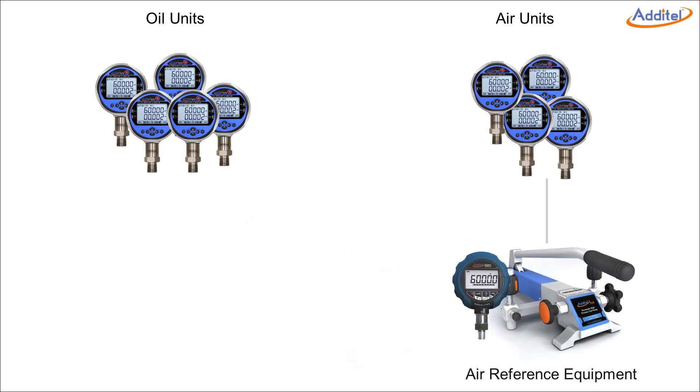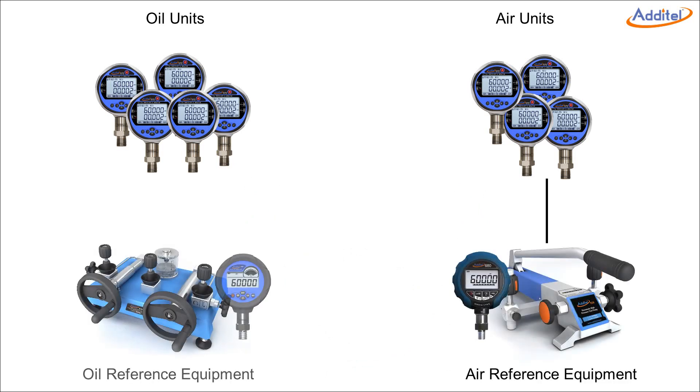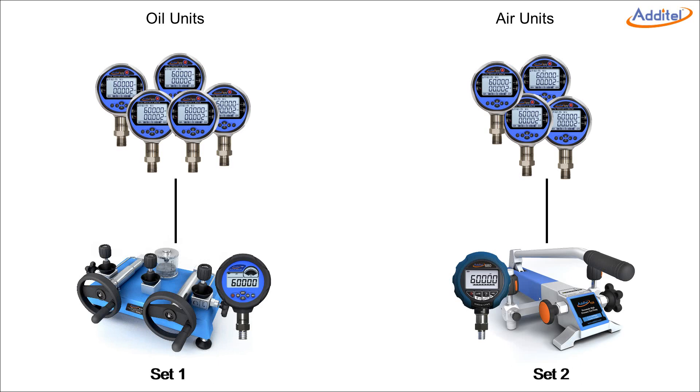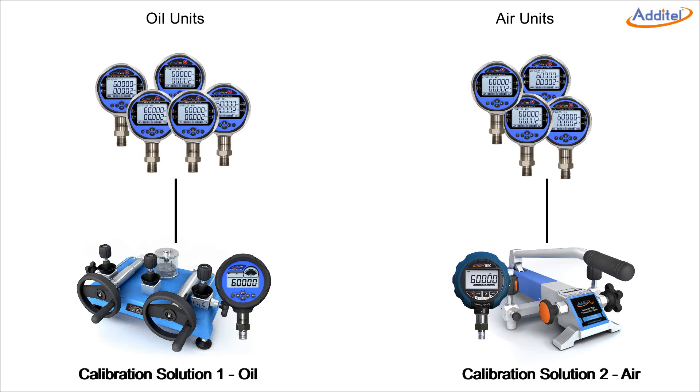Instead, you'll probably have one set of instruments you use to calibrate your air units, and another set of instruments you use to calibrate your oil units. A separate set of units for each type. In ACAL, these separate sets of units are called calibration solutions.